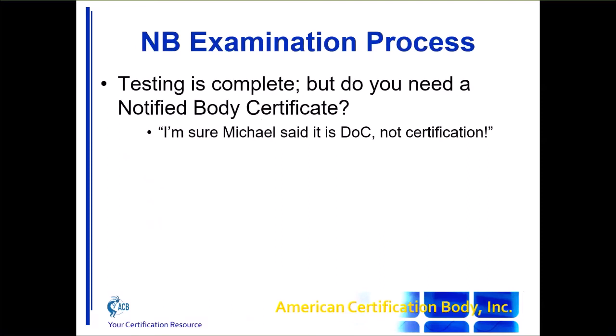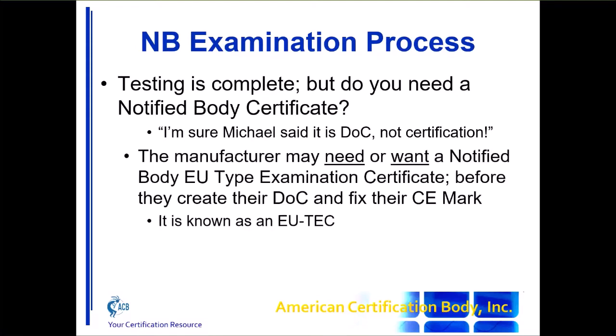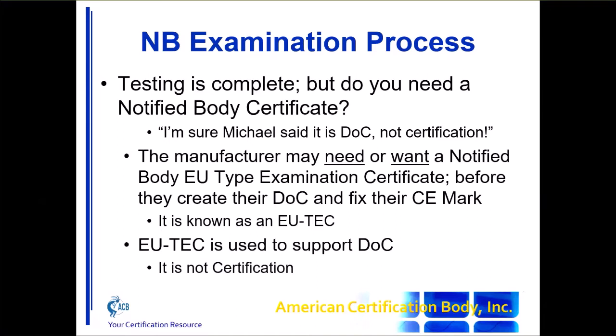So the notified body certificate is not a certification. It's a type examination certificate, kind of like the notified body saying, I've reviewed your product, and based on my examination, here is a certificate to say I think your product meets the requirements of the RED. It's known as an EU-TEC, and it's used to support the manufacturer's decision to sign their DOC. It's not a certification, although it is a certificate.